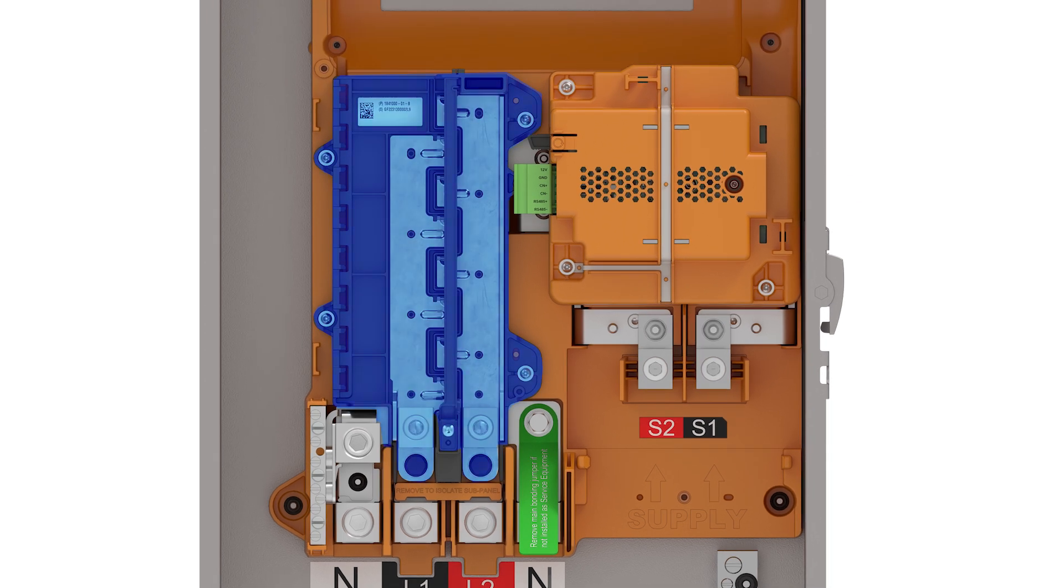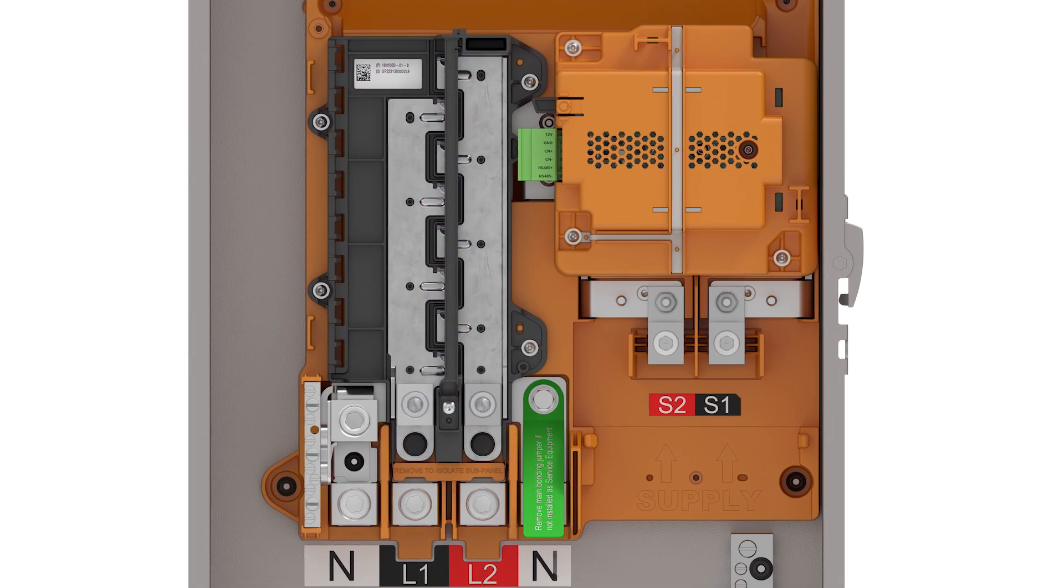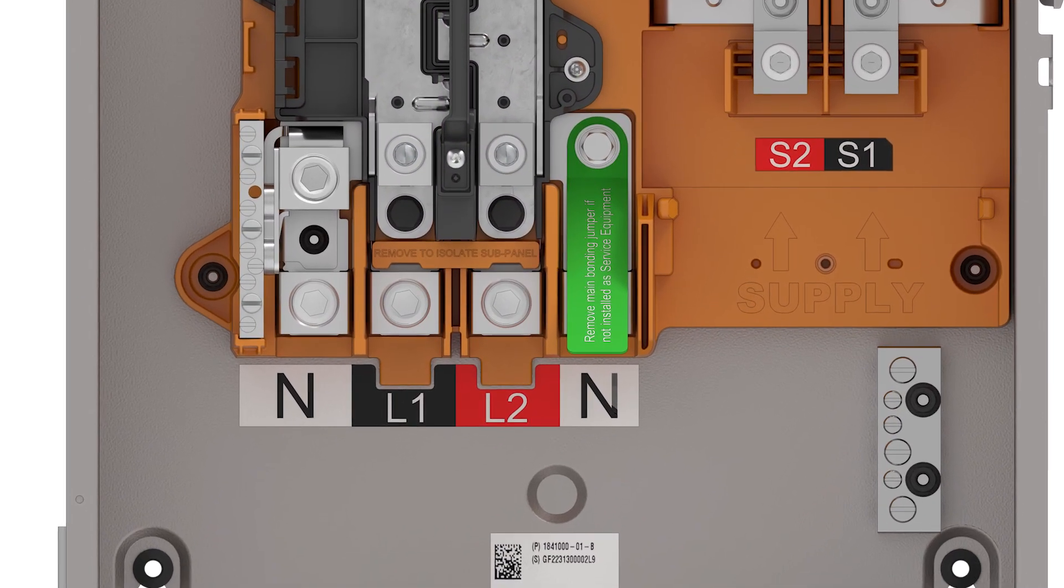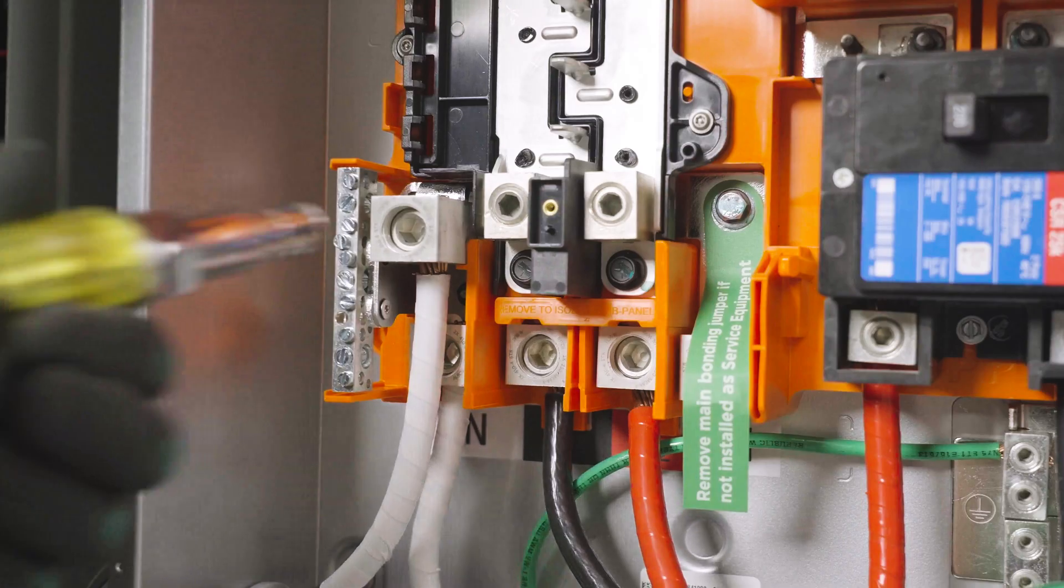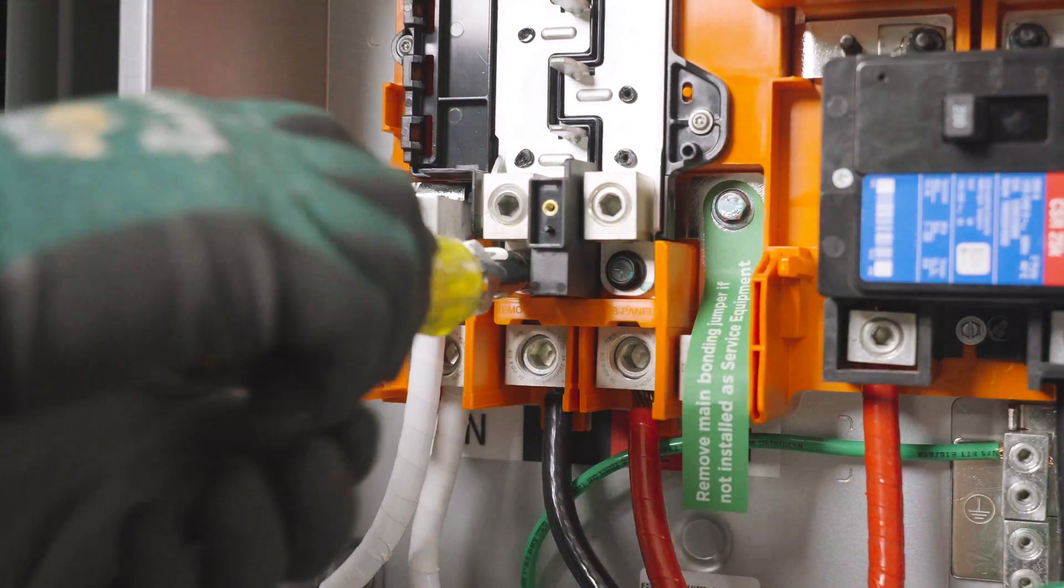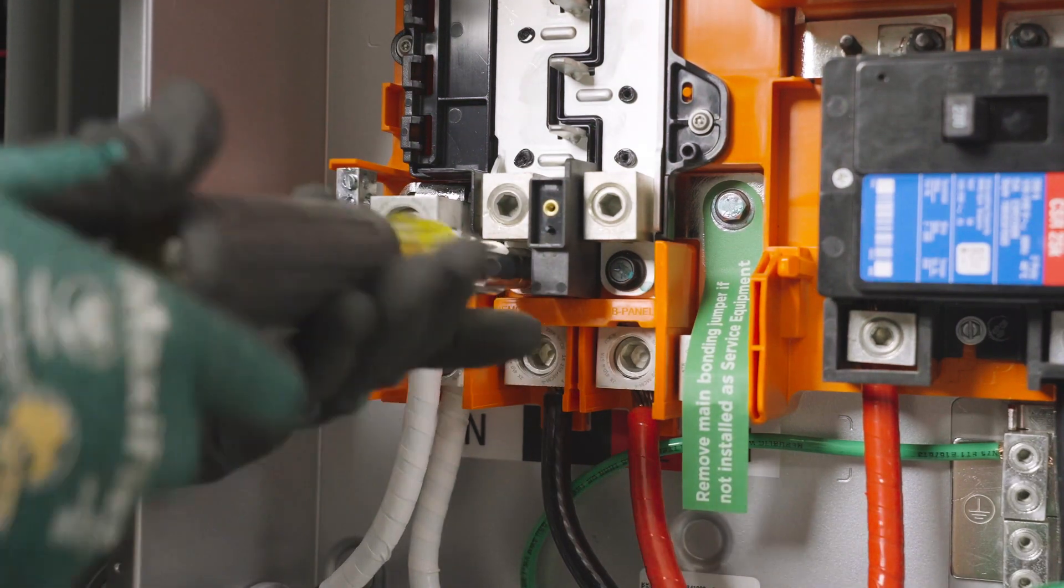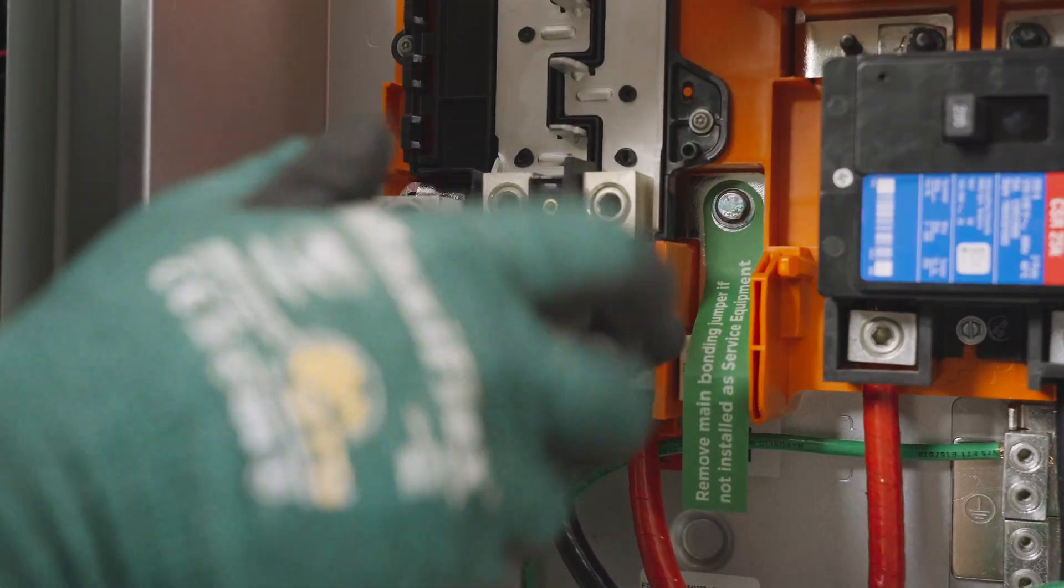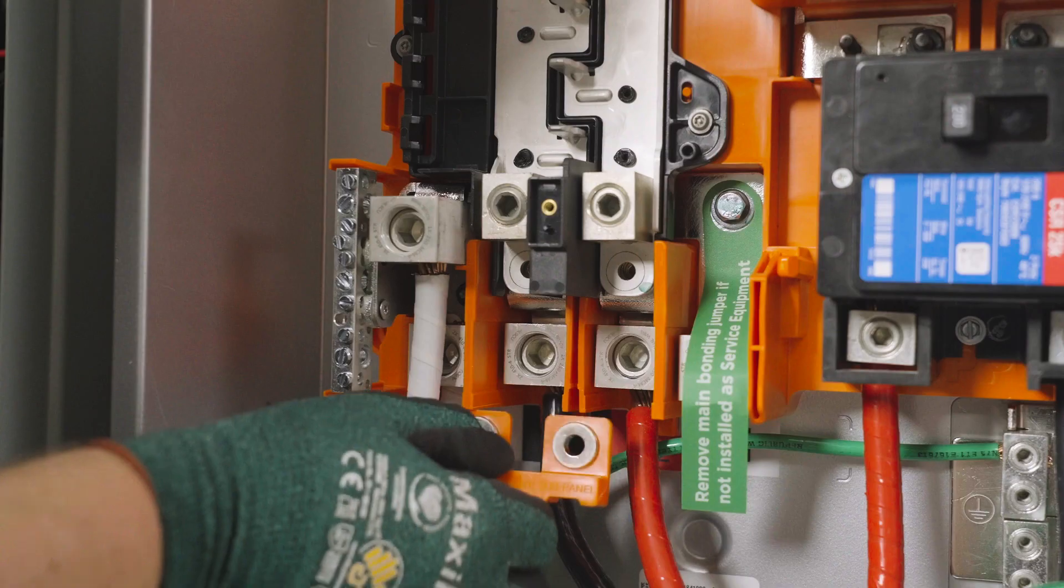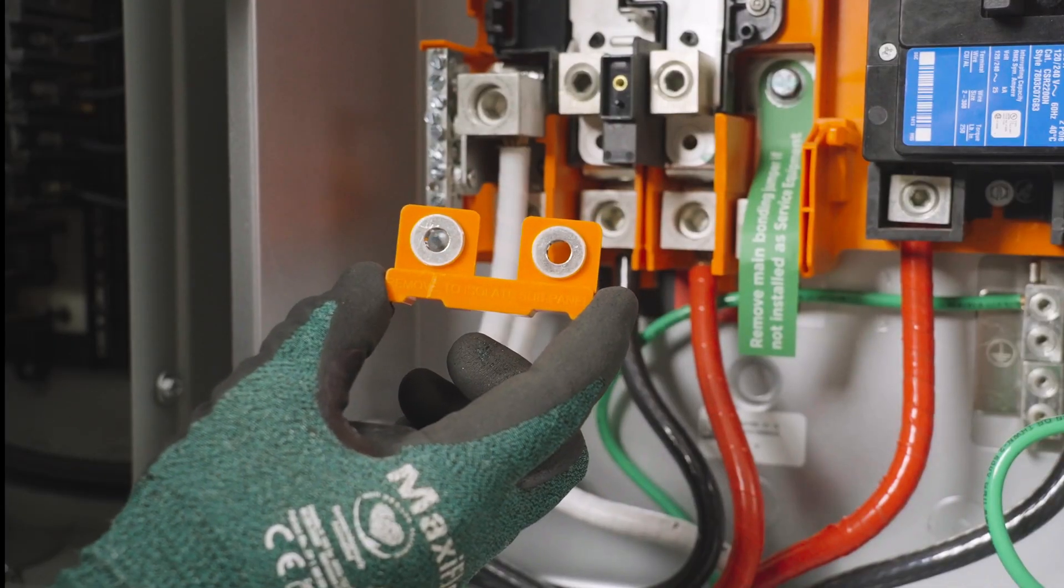The internal panel board is 200 amp rated and supports eight Eaton, Siemens, or Square D breakers. The internal panel board is the preferred location for the breaker for Powerwall and wall connector. Under the internal panel board's lugs, this jumper is factory installed, connecting the internal panel board bussing to the backup bussing. The jumper should only be removed to isolate the internal panel board from the backup lugs, typically when local code requires a line voltage disconnect before power generation breakers.